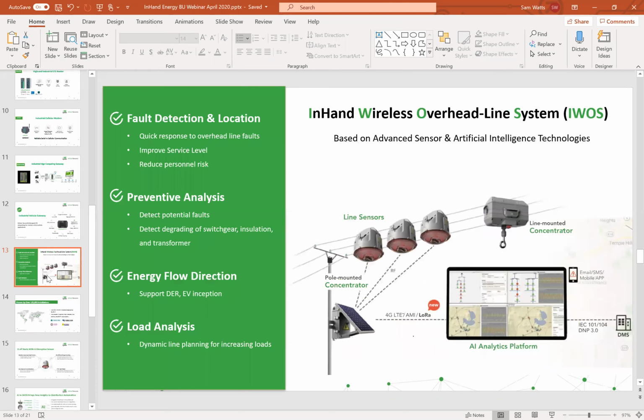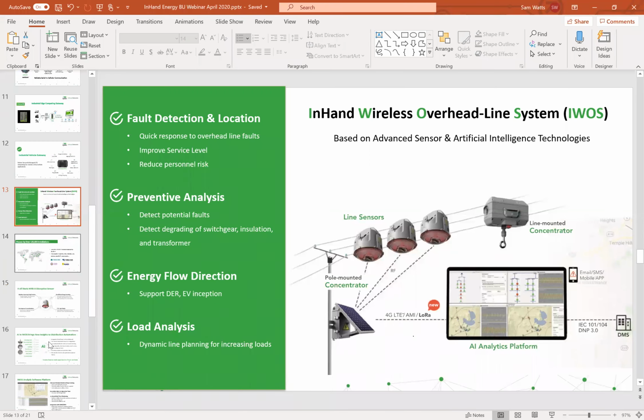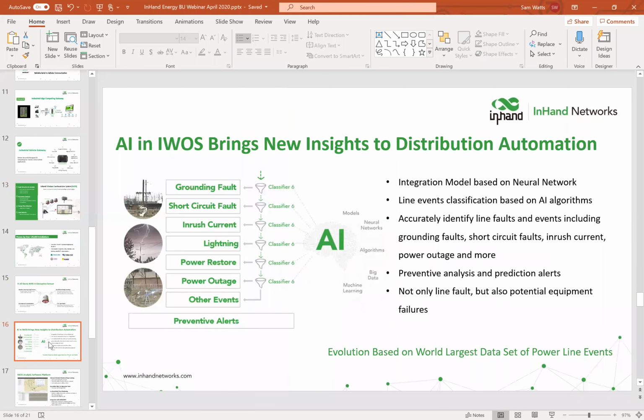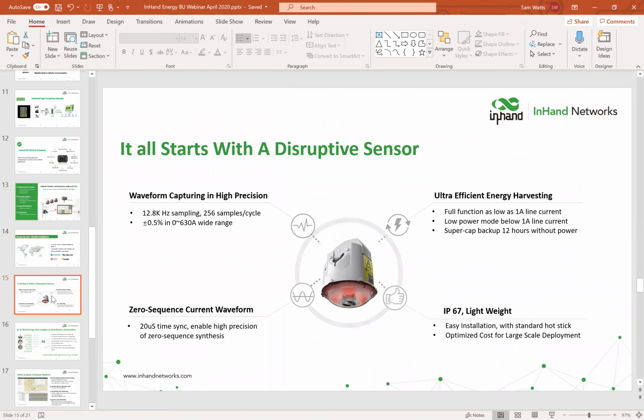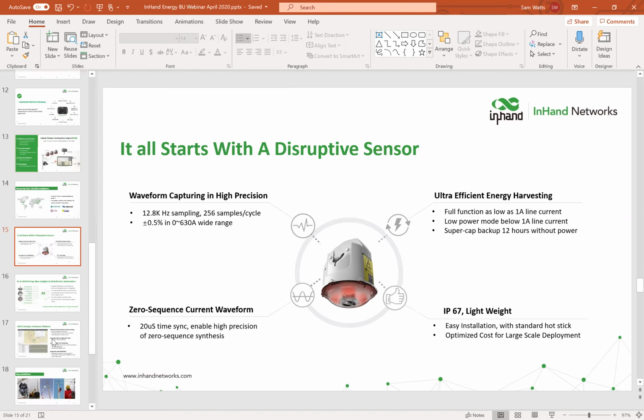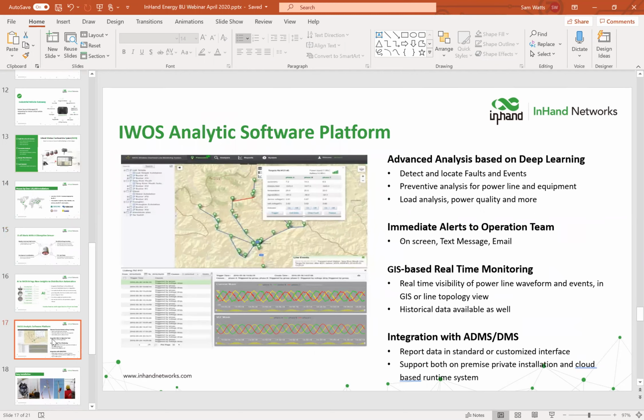We also took a look at the overhead line sensors, 10 kV to 35 kV, inexpensive, featuring a patented algorithm to pick up common faults and condition monitoring indices on the line. These are technically advanced, functioning down to an industry leading 1 amp of line current at high precision, with supercapacitor backup, wide temperature ranges, and IP ratings. We also talked about the software and how easy to use it is, coming included with the package.